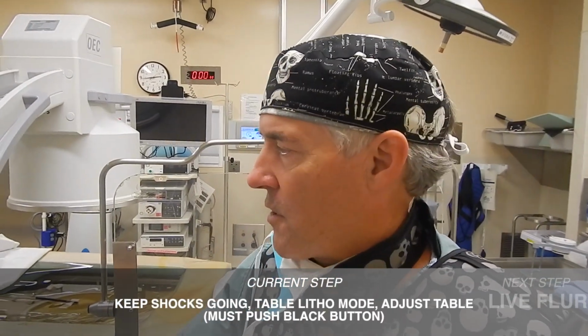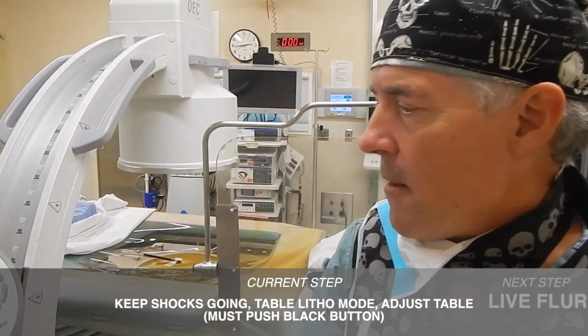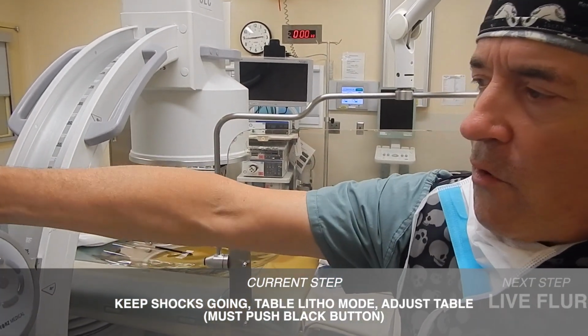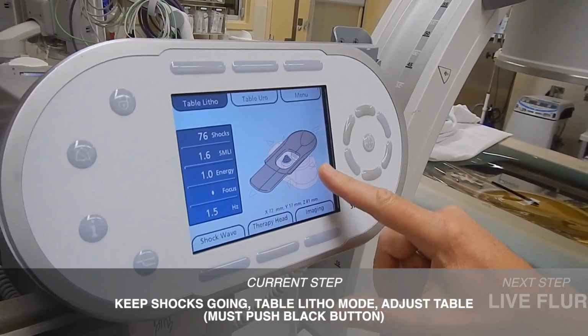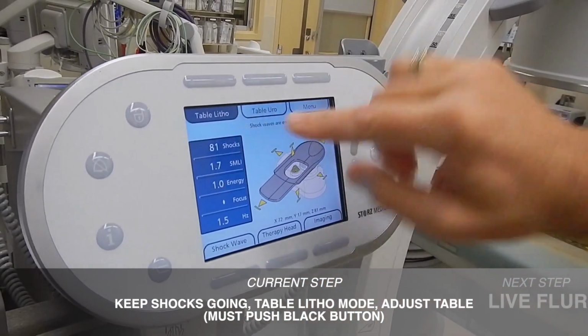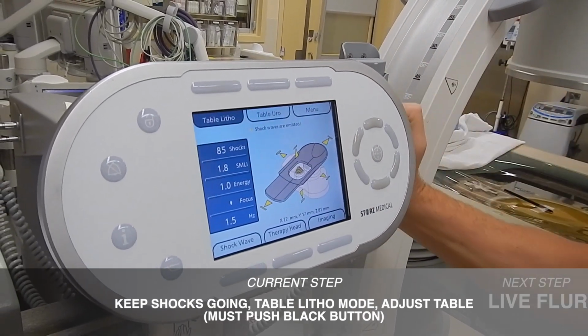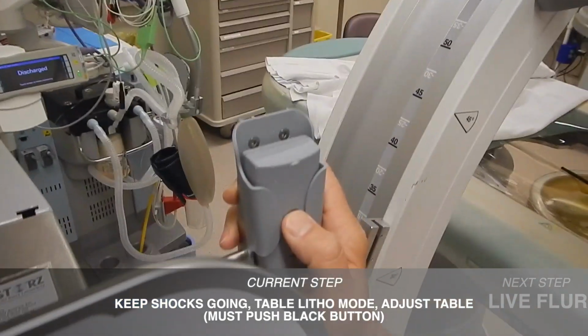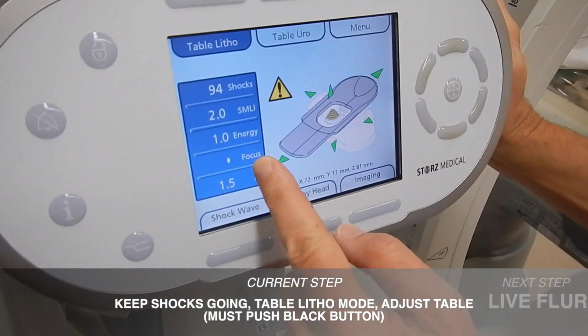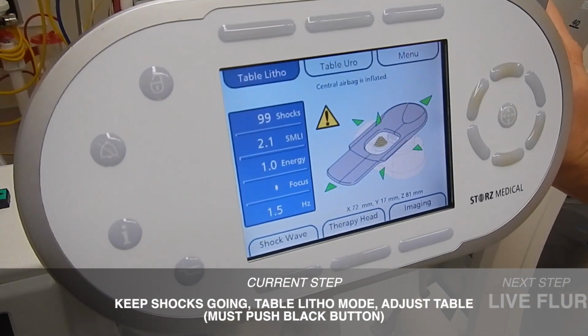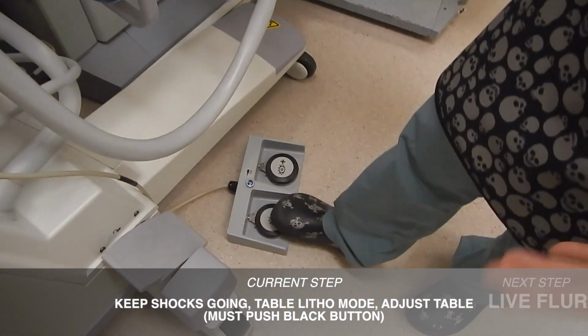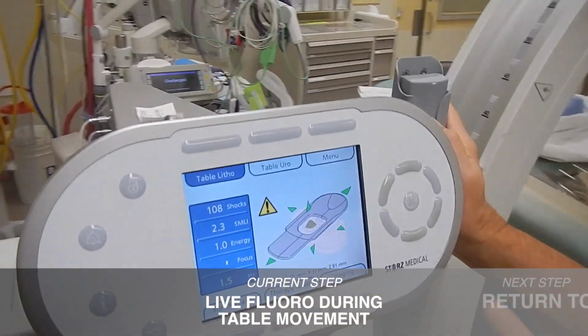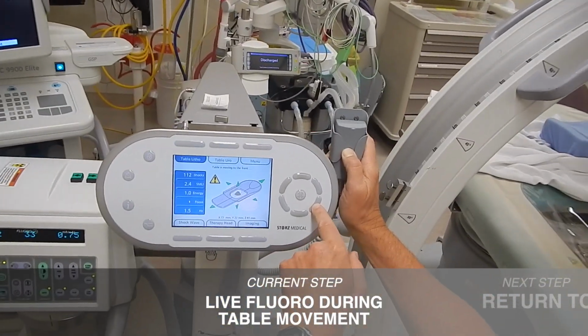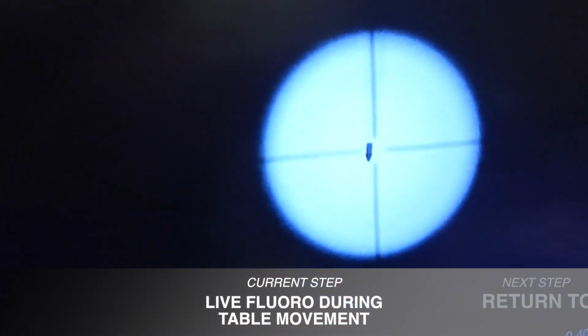If the stone is still getting some shocks, but it's not exactly in the crosshairs, you can keep the shocks going. When table litho gets pressed, you can see that the table movements aren't available. It says shocks are emitted. That's okay. All you have to do is press this black button and hold it. The green lights come on for the arrows, and that's why we have the foot pedal available, because you need two hands for this. So we're holding the black button, I'm going to fluoro, and I'm going to move the stone. You'll find you'll be doing a lot of that during the procedure, so it's good to know.